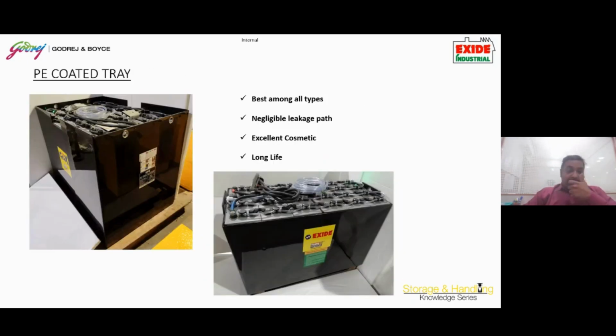Now we also have a PE coated tray. As I explained, there might be a leakage current. Leakage current happens when electrolyte spillage happens, and if it is a metal tray, the spillage forms a corrosive path, and the current tends to leak from the cells through the electrolyte and the corrosive path into the ground. This causes leakage. However, a PE coated tray is highly resistant to acid, so there will not be the leakage. Though there may be some leakage, it will be negligible and not significant, and it will also go away if we do regular washing of the cells.